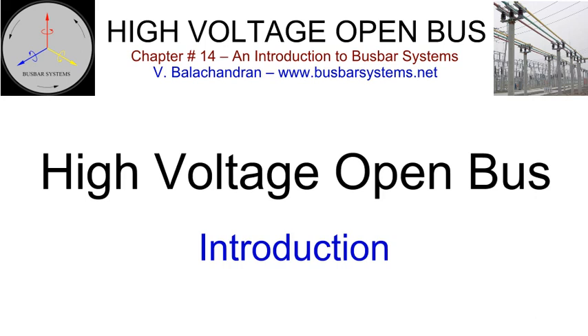Before the introduction of the gas-insulated switchgear, a few high-voltage switchyards in coastal areas, exposed to winds and salty atmosphere, and areas with heavy pollution had been housed in buildings. The high-voltage lines entered and exited the building through high-voltage condenser bushings or by cables. Switchyards with a rigid bus are more compact with a low support structure and lesser phase-to-phase clearance when compared to those with strain bus. However, a strain bus offers better seismic force withstand capability than a rigid bus.